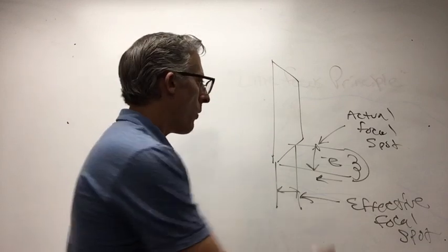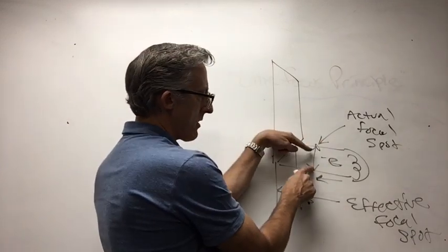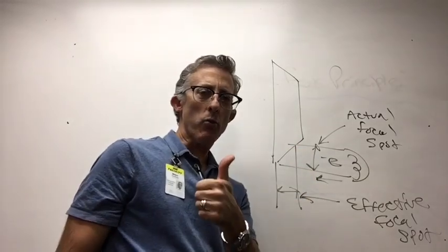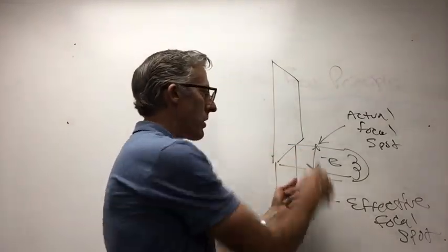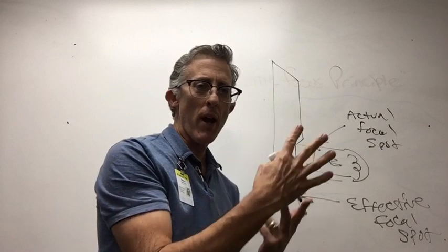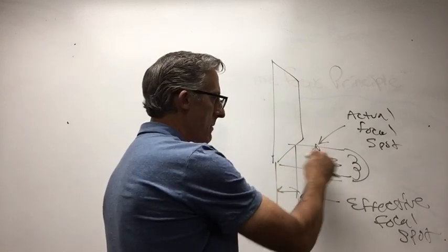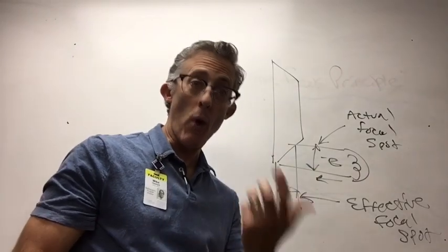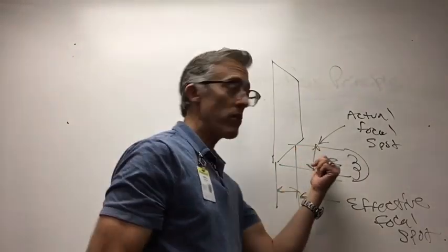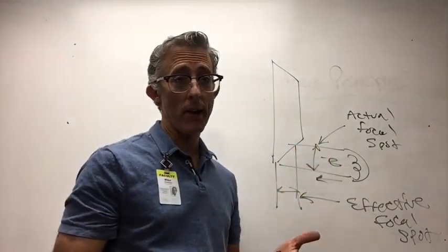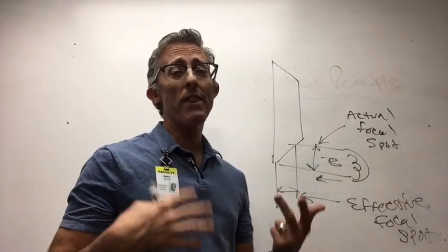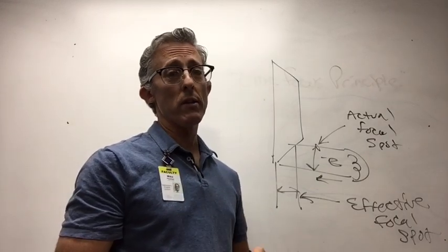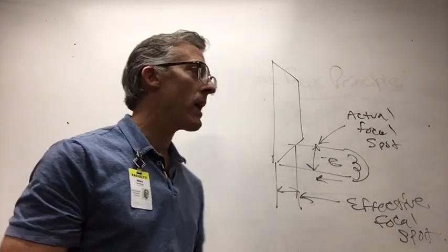First, let's back up a little bit. Why not just make this width of the actual focal spot really narrow? Here's why. We want to, as much as we can, spread this electron beam out over the surface of the target area of the anode. Why? Because these electrons are moving at about half the speed of light, they're being pushed by thousands of volts, and then they're slamming into this anode surface. You know what? X-ray tubes are expensive. We want to preserve them as much as we possibly can.